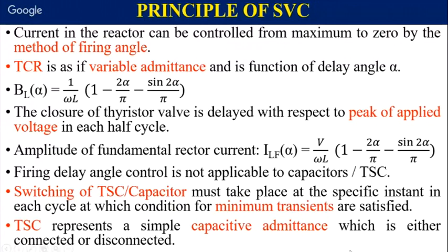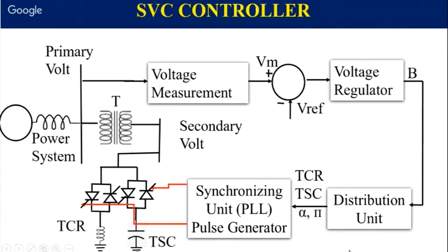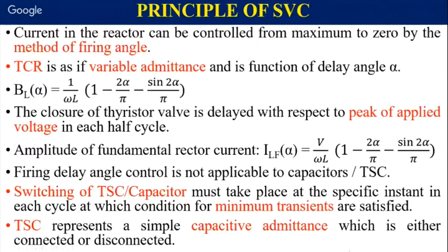Firing angle control is not applicable in the case of a capacitor, as we have discussed. The capacitor bank should be switched on and off when there is minimum transient, or in other words, minimum voltage across the switches, meaning semiconductor devices. So a TSC, thyristor switched capacitor, represents a simple capacitive admittance which is either connected or disconnected.